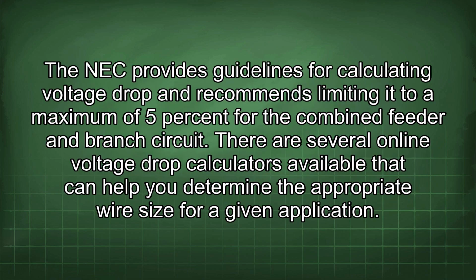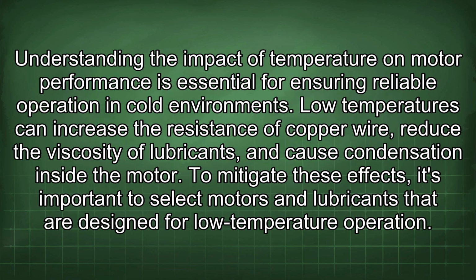The NEC provides guidelines for calculating voltage drop and recommends limiting it to a maximum of 5% for the combined feeder and branch circuit. There are several online voltage drop calculators available that can help you determine the appropriate wire size for a given application. Understanding the impact of temperature on motor performance is essential for ensuring reliable operation in cold environments.